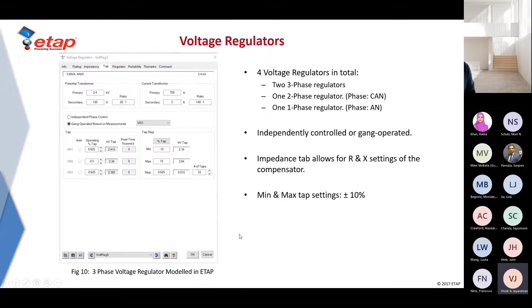The next is voltage regulators, and there are 4 voltage regulators in total. This system has 2 3-phase regulators, one 2-phase regulator, and one single-phase regulator. Now, the tab independently controlled or gang operated can be used from here. So in this case, voltage regulator 5, which is 1 in the system, operates all the 3 phases simply based on the measurements from phase A. And the total tap settings are plus or minus 10%. And the impedance tab that you see here right next to tap allows for R and X settings for the compensator.